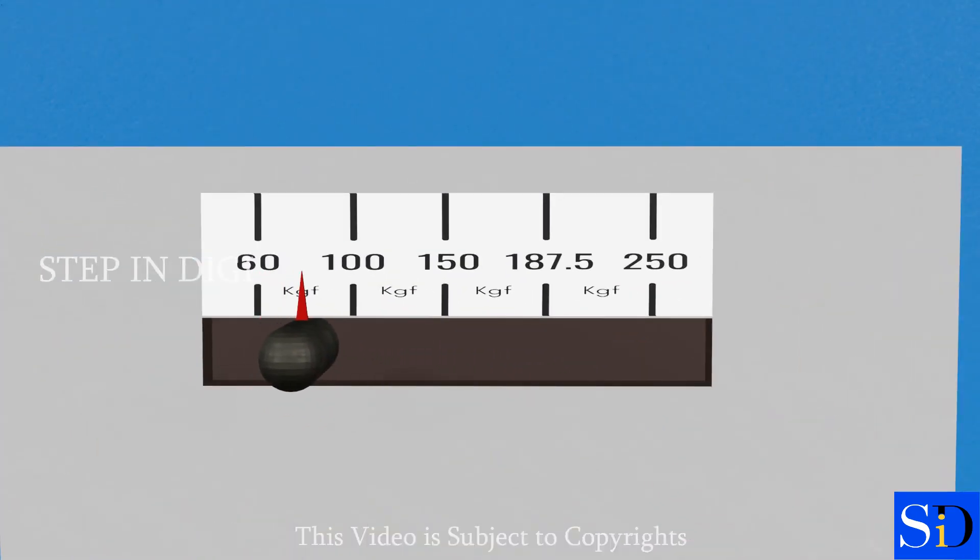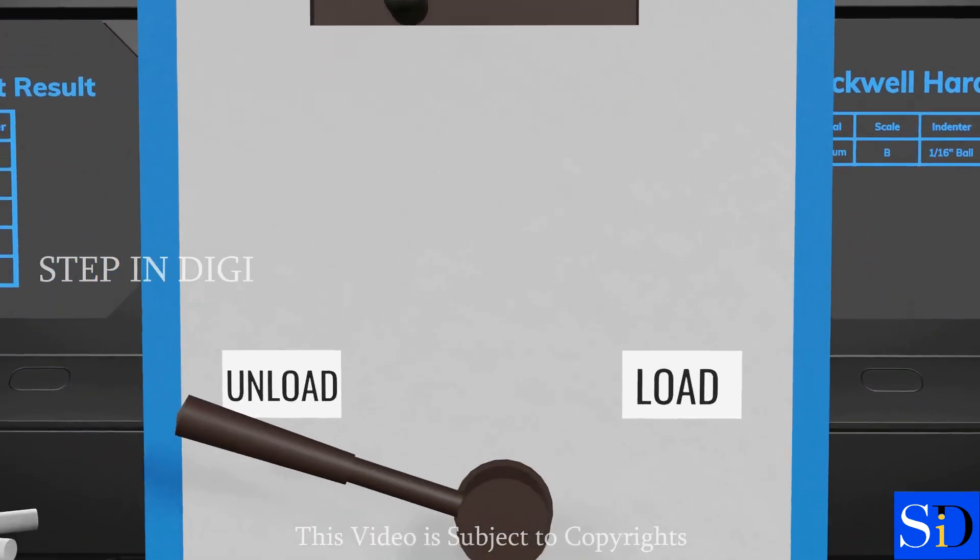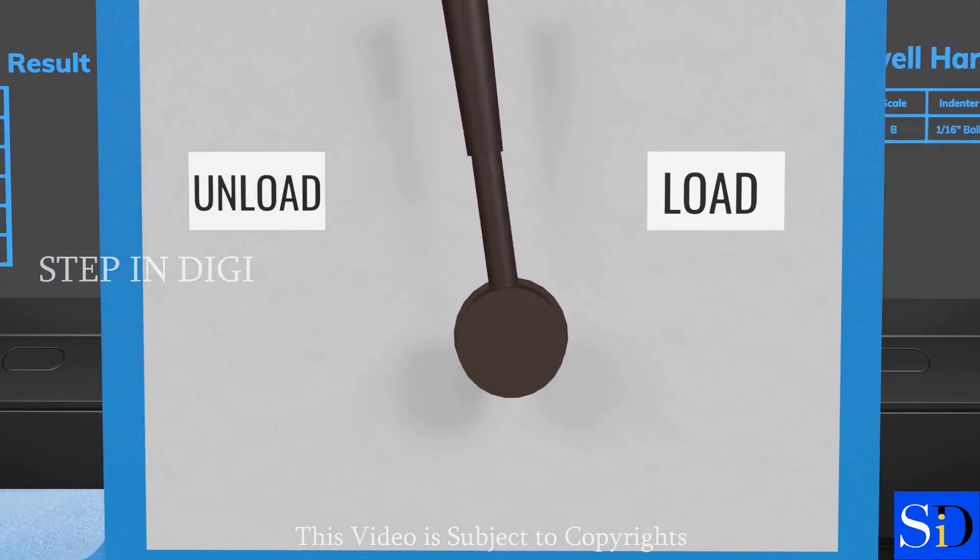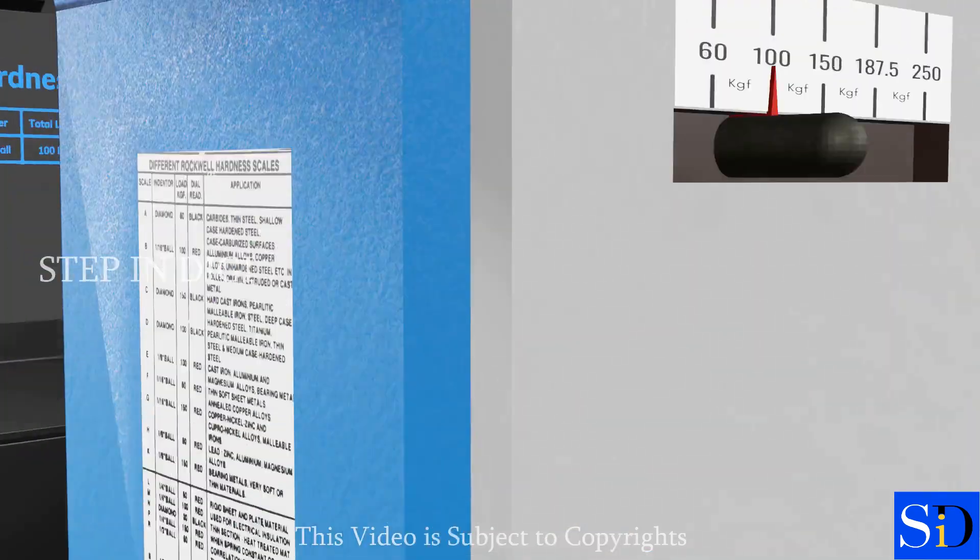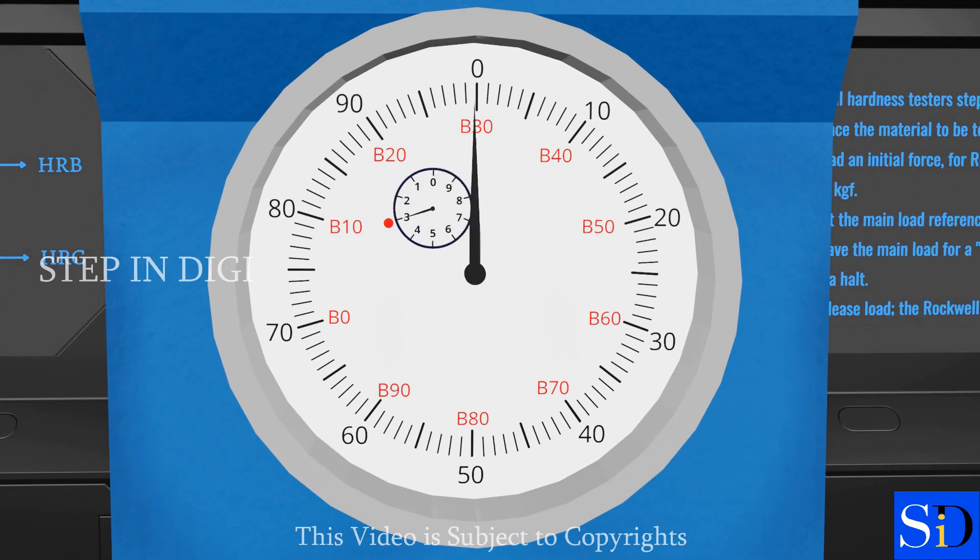Now, initialize the load of 100 kgf using the switch given. Push the lever towards the load side gently, and leave the main load for a dwell time sufficient for indentation to come to a halt.